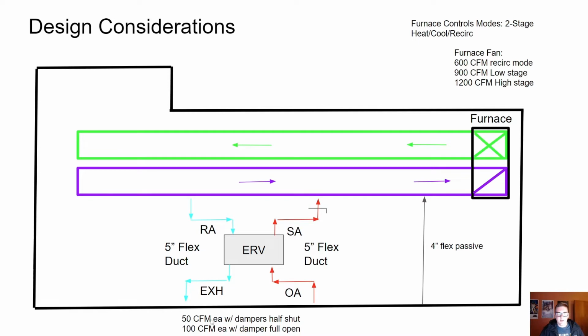And then this down here is my ERV. Before we get into that, in most homes where builders at least tried to provide you some outdoor air, if you look on the return side of your furnace, you've probably got about a 4-inch flex duct that is probably snaked all through the basement. It makes its way to an inlet, a louver on the side of your wall. And in my case, they put that louver, but then they built a deck over it, so I was getting almost no airflow.